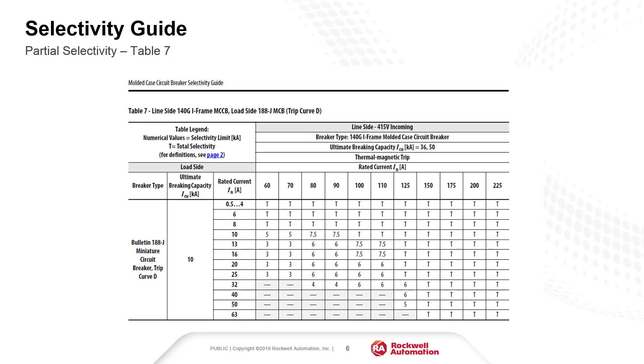Let's look at our table again. This time, let's assume the load side is at 13A for the 188J breaker and still at 100A for the 140G breaker. We have partial selectivity, since our selectivity value is 7.5 kA between the two circuit breakers.